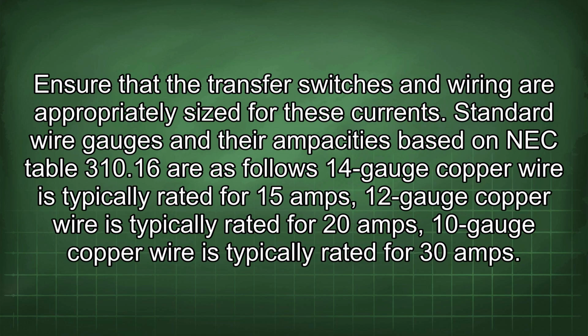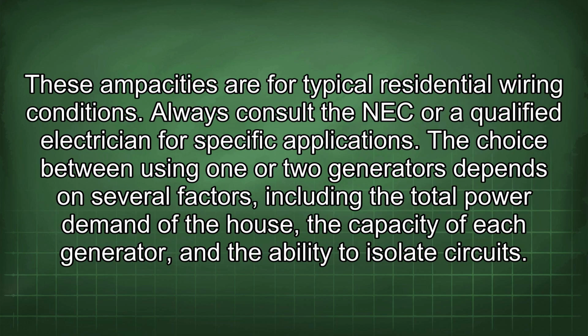Ensure that the transfer switches and wiring are appropriately sized for these currents. Standard wire gauges and their ampacities based on NEC table 310.16 are as follows. 14 gauge copper wire is typically rated for 15 amps, 12 gauge copper wire is typically rated for 20 amps, 10 gauge copper wire is typically rated for 30 amps. These ampacities are for typical residential wiring conditions. Always consult the NEC or a qualified electrician for specific applications.